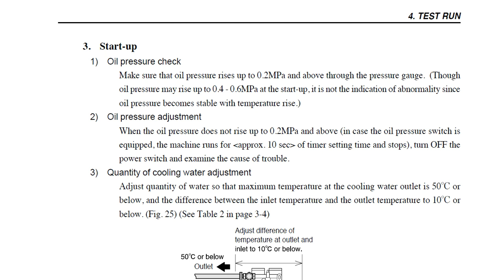The next step: we check that the oil pressure adjustment is proper. When the oil pressure does not rise up to 0.2 megapascals and above, in case the oil pressure switch is equipped, the machine runs for approximately 10 seconds timer set time and stops. Turn off the power switch and examine the cause of trouble. If the pressure does not rise, there is a protection for the air compressor and we need to find the cause.